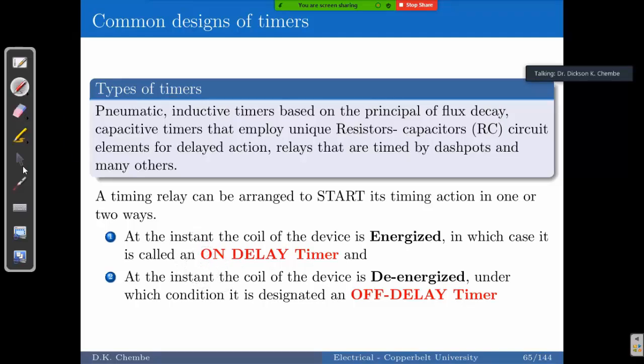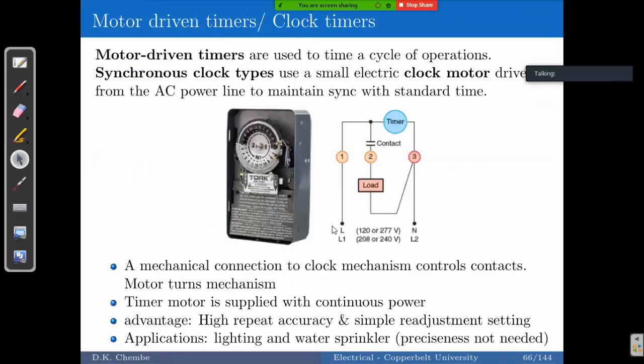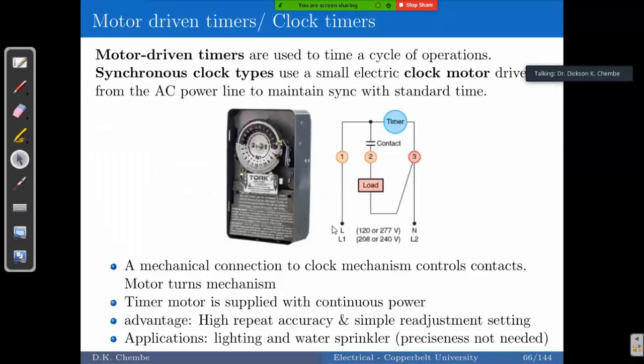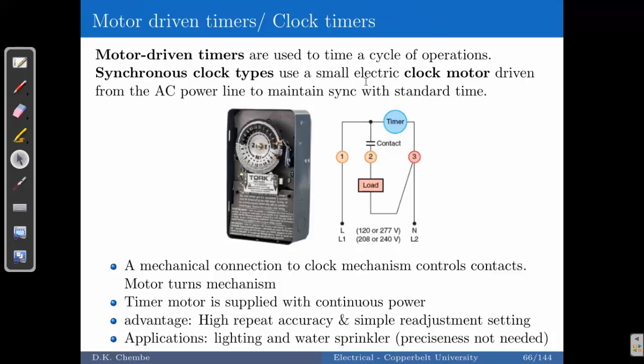We start looking at the types of timers, beginning with motor-driven timers. Motor-driven timers usually use small synchronous clock motors that drive the timing action. There is a mechanical connection to the clock which controls the contacts. The synchronous motor will maintain the sync of time as it rotates, and there is a gear ratio in place so that as it rotates, the clock timing is working as well.